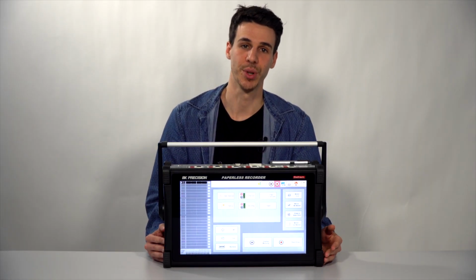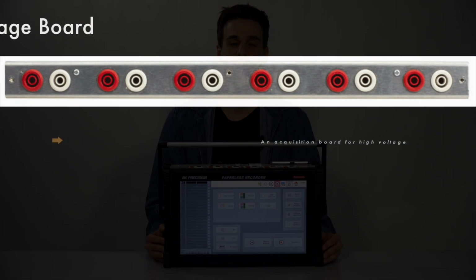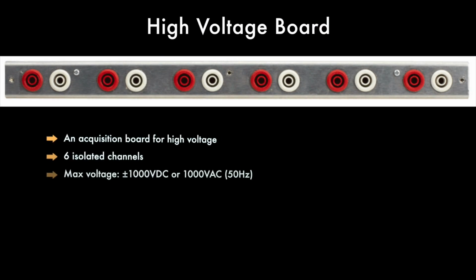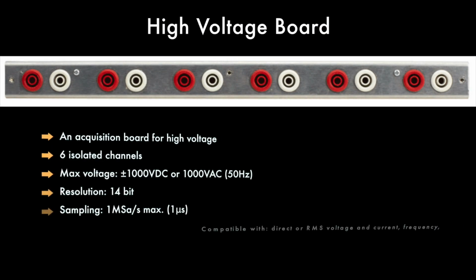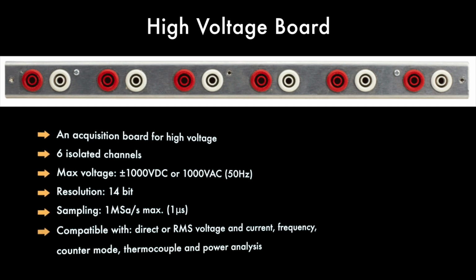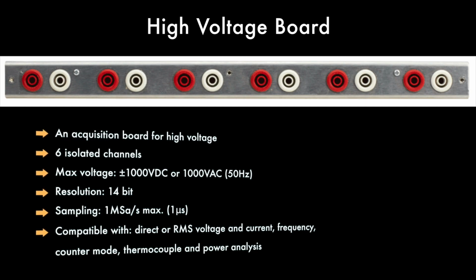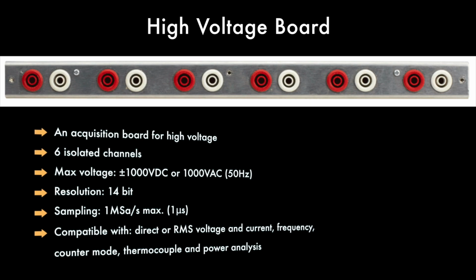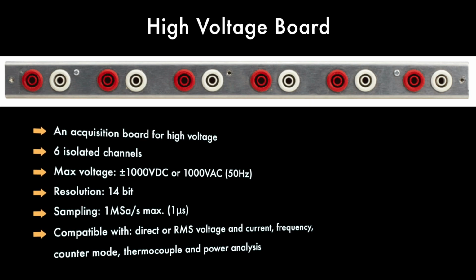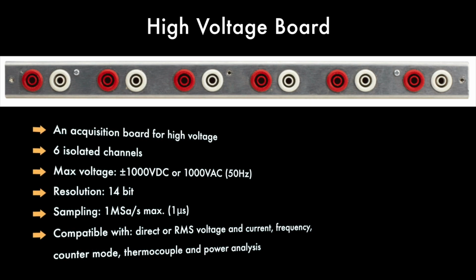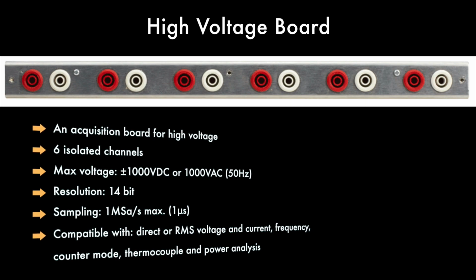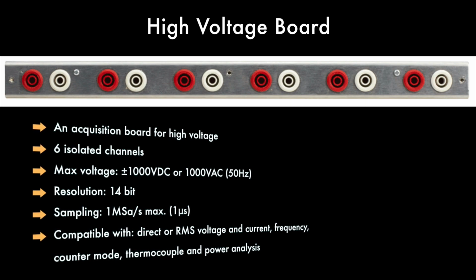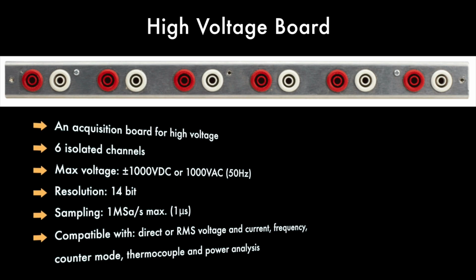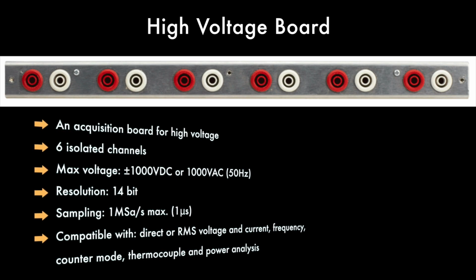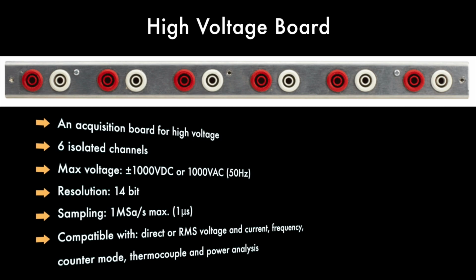For the high voltage board. The high voltage board is made for high voltage measurements. It has 6 isolated channels, a maximum voltage input of plus and minus 1000 volts, a 14-bit resolution, and a maximum sampling rate of 1 megasample per second. This board is compatible with DC or RMS voltage, current, frequency, and power analysis on single and 3-phase networks.